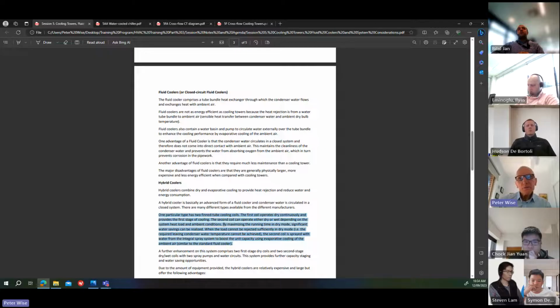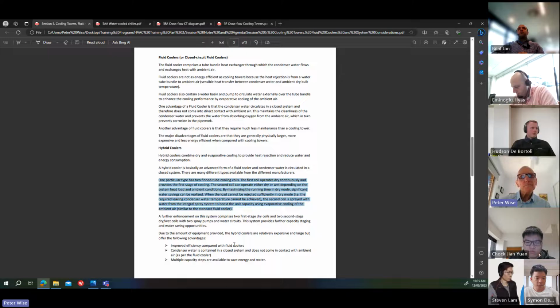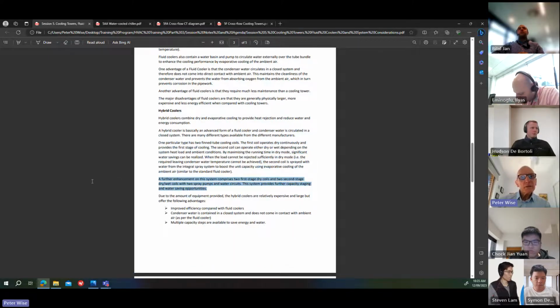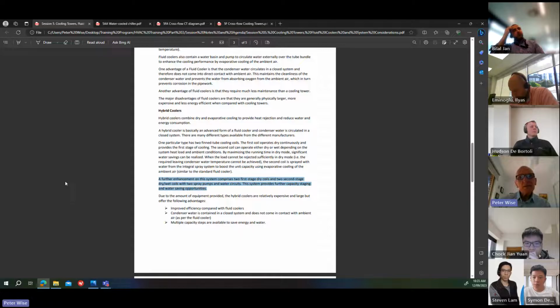By maximising the running time in dry mode, significant water savings can be realised. When the load cannot be rejected sufficiently in dry mode, in other words, you can't achieve the required leaving condenser water temperature, the second coil is sprayed with water from the integral spray system to boost the unit capacity using evaporative cooling of the ambient air, similar to a standard fluid cooler. If you look at these, they can get quite complex, and they're quite expensive and quite large, but they have energy efficiency advantages over a standard fluid cooler.